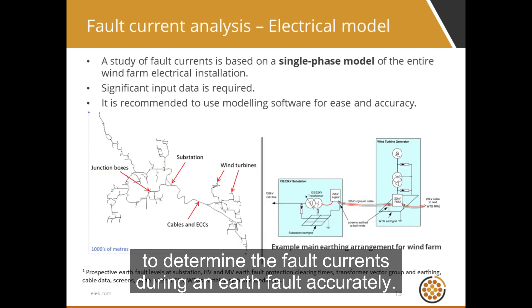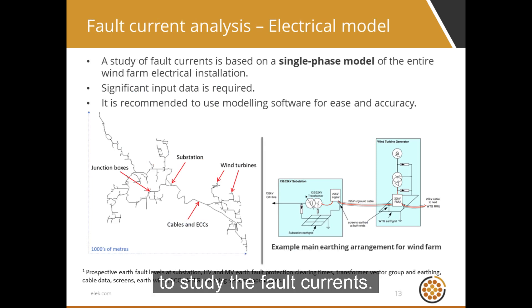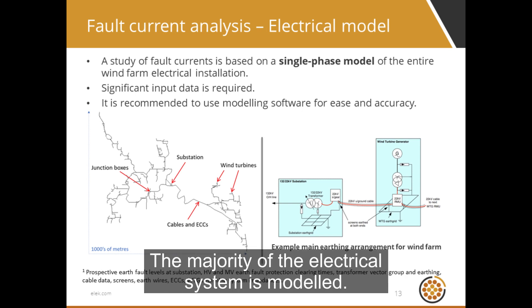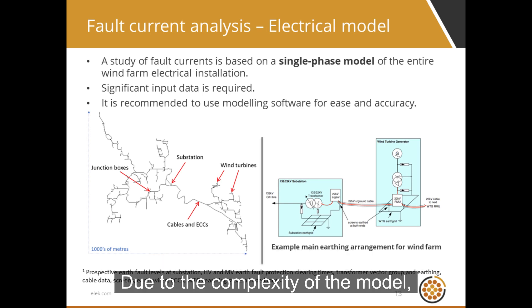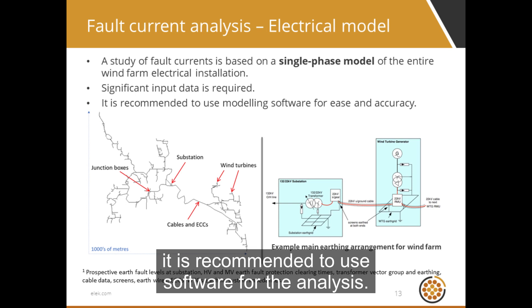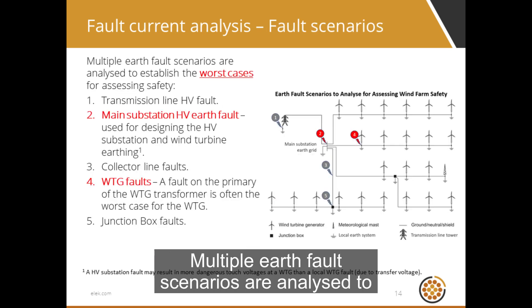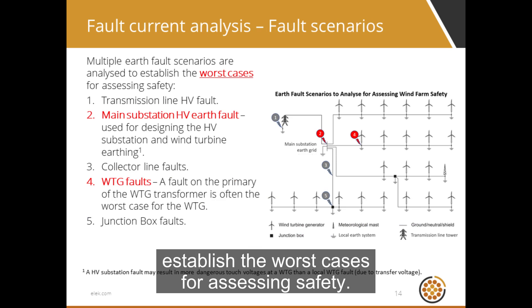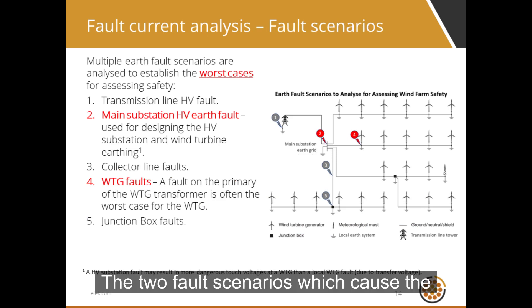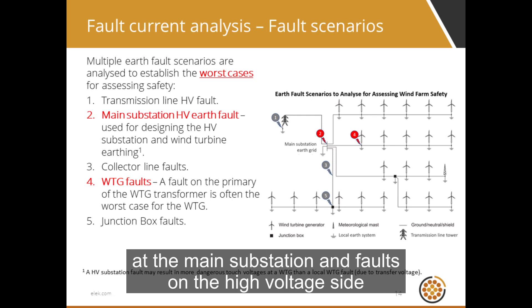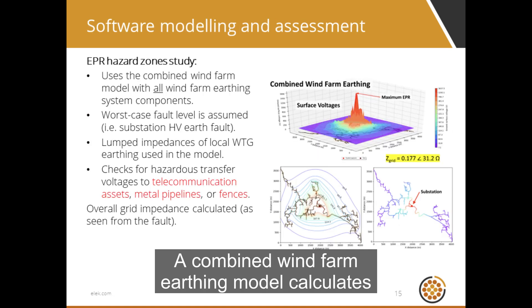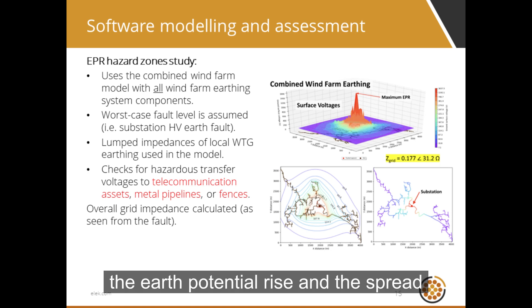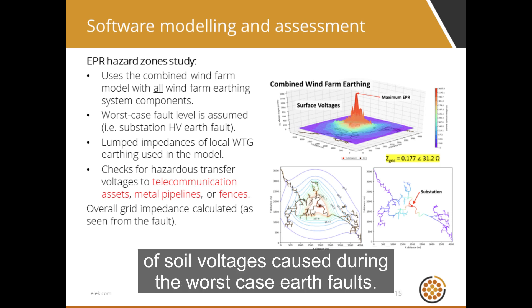To design the earthing, it is important to determine the fault currents during an earth fault accurately. A single-phase electrical model is used to study the fault currents, and the majority of the electrical system is modeled, requiring a significant amount of input data. Due to the complexity of the model, it is recommended to use software for the analysis. Multiple earth fault scenarios are analyzed to establish the worst cases for assessing safety. The two fault scenarios which cause the highest touch voltage hazards are generally high-voltage earth faults at the main substation, and faults on the high-voltage side of the wind turbine generator transformers. A combined wind farm earthing model calculates the earth potential rise and the spread of soil voltages caused during worst-case earth faults.